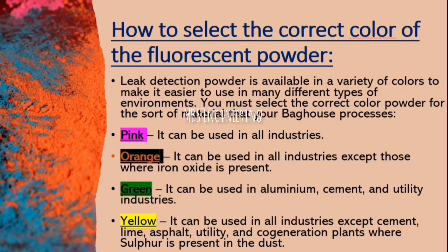Now, how to select the correct color of fluorescent leak detection powder. Leak detection powder is available in a variety of colors to make it easier to use in many different types of environments. You must select the correct color powder for the sort of material that your bag house processes. Pink color can be used in all industries. Orange color can be used in all industries except those where iron oxide is present. Green color can be used in aluminum, cement, and utility industries. Yellow color can be used in all industries except cement, lime, asphalt, utility, and cogeneration plants where sulfur is present in the dust.